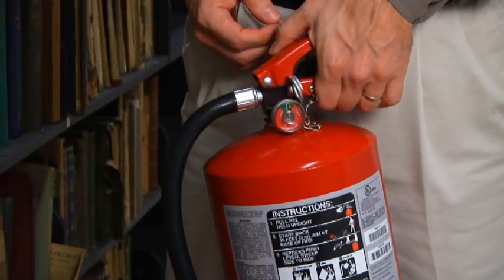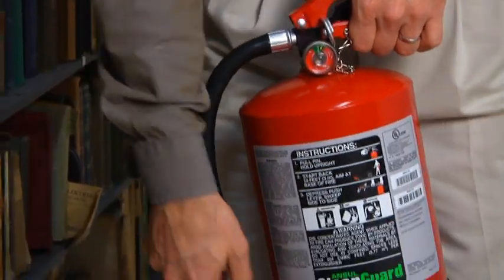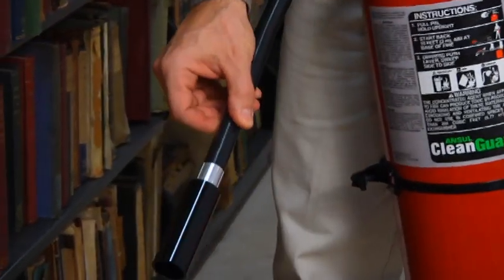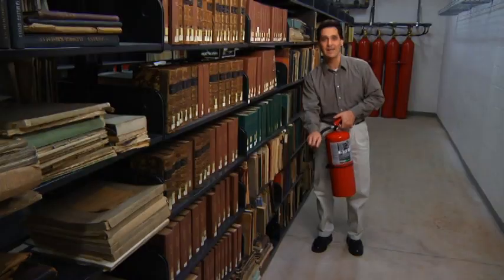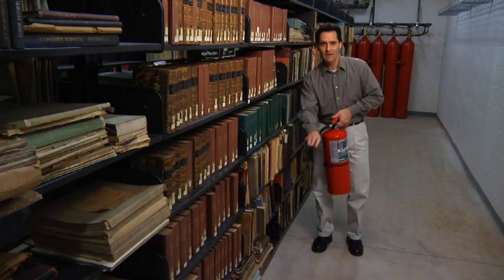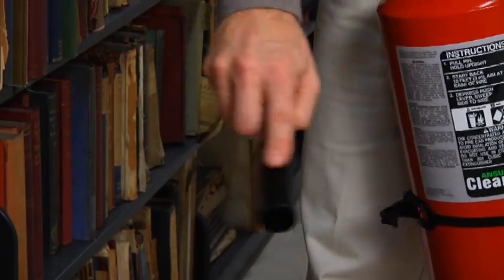To use this Ansul extinguisher, place it in one hand and remove the ring pin. Then, remove the hose from the hose retainer. Place your finger alongside the nozzle tip to help direct the agent onto the hazard. Next, depress the lever and aim the agent at the base of the fire, sweeping side to side until the fire is out.